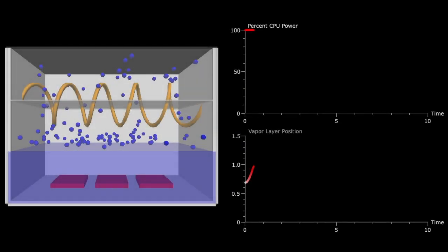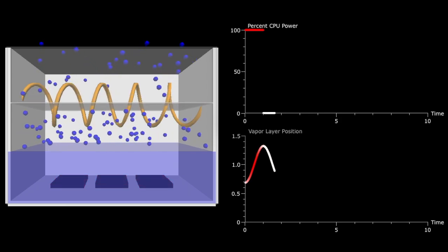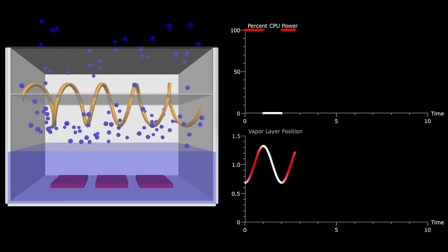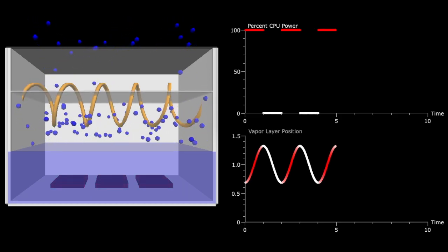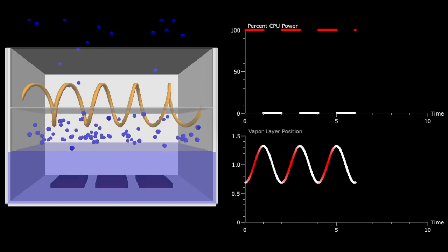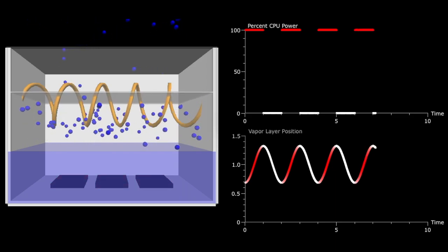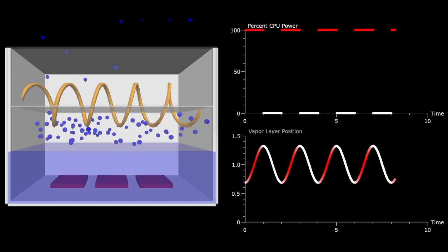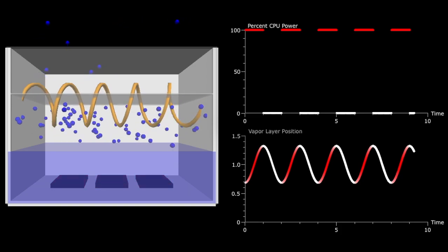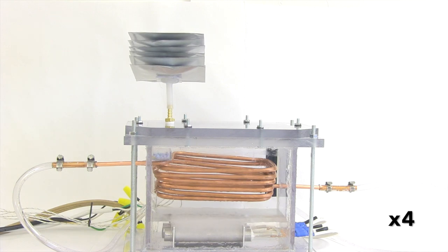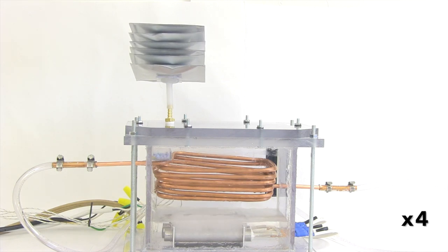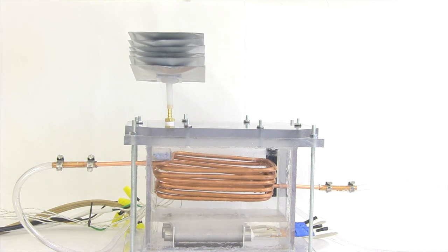Unfortunately, even after the vapor layer stops rising, there is still the possibility of fluid loss. When the system is in operation, the power delivered by the electronics is not constant. As it fluctuates, the vapor level rises and falls. When power increases, vapor from the headspace is pushed out. When the power decreases, air is pulled in. This motion is seen in the inflation and deflation of the bellows as shown. Without proper mitigation techniques, this causes small amounts of fluid to be lost, which, over time, can result in significant fluid loss.